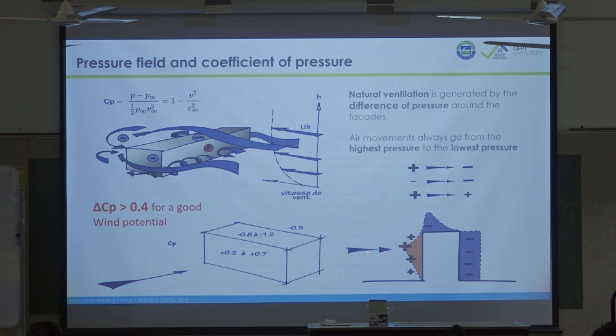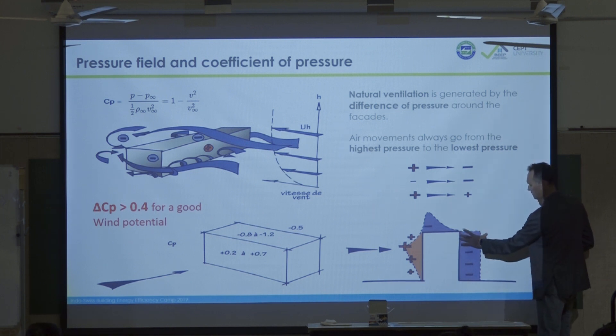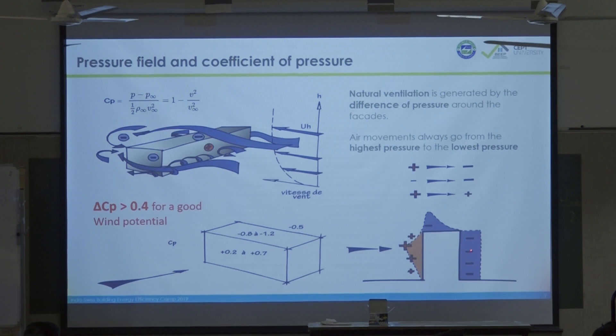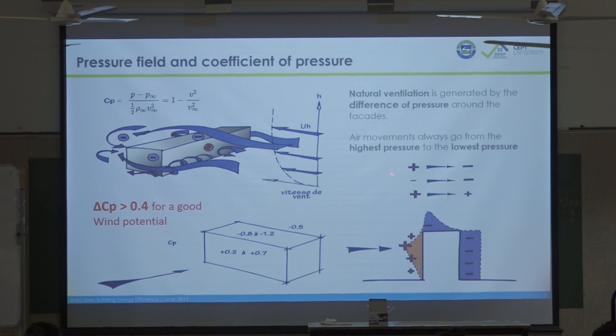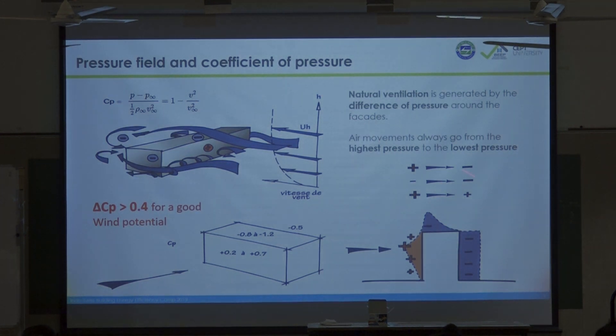So what is important: you have a high pressure windward and a low pressure leeward, and the profile is constant windward. With a higher building this low pressure value is more important, so you can generate a higher low pressure. The air movement inside the building depends on the difference of those two pressures — the wind always goes from high pressure to low pressure, just like heat flux goes from high to low temperature.